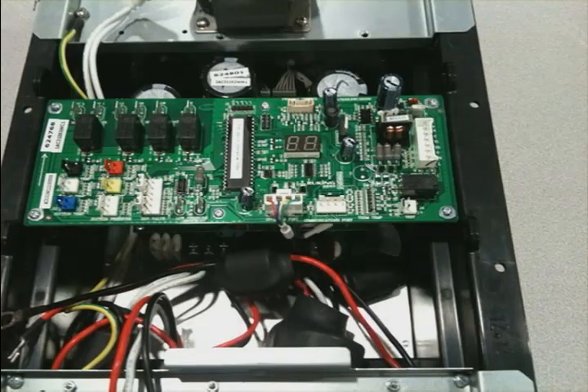If the fuse on the inverter board fails, do not replace the fuse. You'll have to replace the inverter. Keep in mind that there are no serviceable parts on the inverter. The interface board is the brain of the system and works with a 24-volt AC signal from the thermostat. Based on if the thermostat is providing a Y1 or a Y2 input signal, this determines what speed the compressor will be running at in either heat or cool mode.